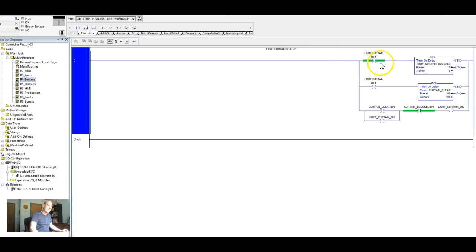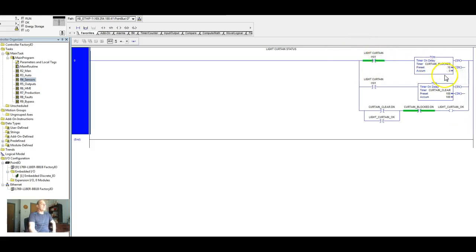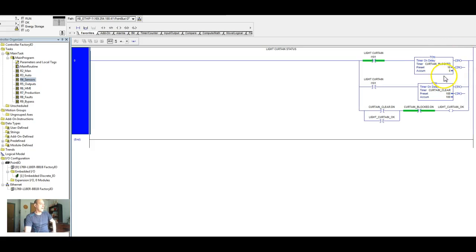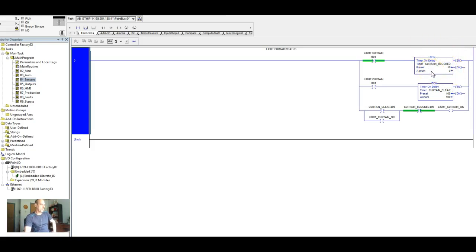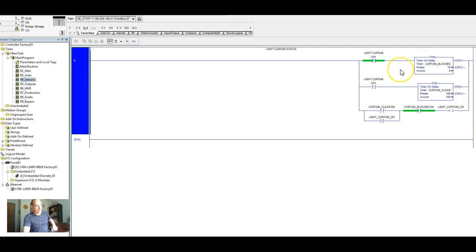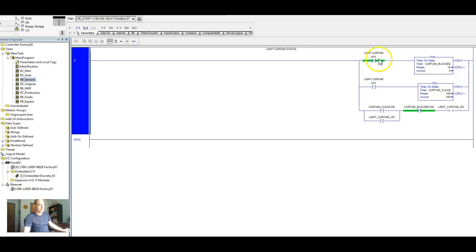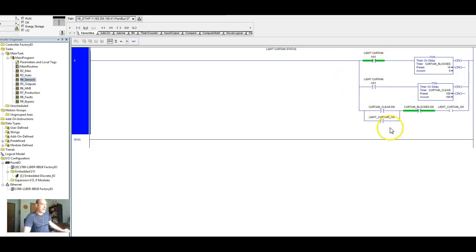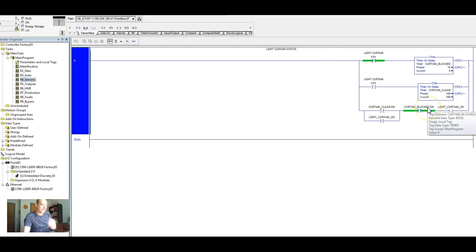Right. Now the second that it gets blocked, we come up here and our curtain gets blocked. And we put a tiny little timer here, just a tiny little one. So if it gets blocked for virtually almost nothing, we're going to be okay. But if it gets blocked in a real world, then this timer's going to timeout and we're going to get our light curtain is going to drop out.